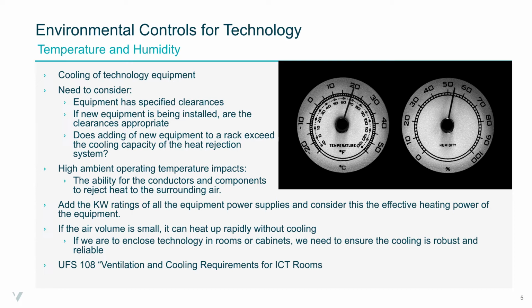So high ambient operating temperature impacts the ability for conductors and components to reject their heat into the surrounding air. And as a general rule of thumb, if you add up all the kilowatt ratings of the equipment and the power supplies, that's the effective heating power of all the equipment. There needs to be equivalent cooling power to keep that temperature at an acceptable level. If the air volume is small, if you've got a lot of equipment in a small room, small area, small compartment, it can heat up rapidly.